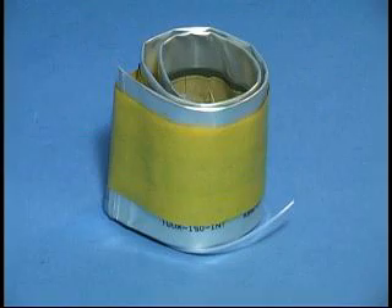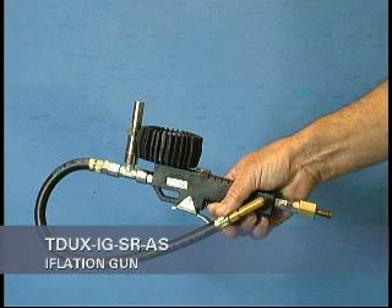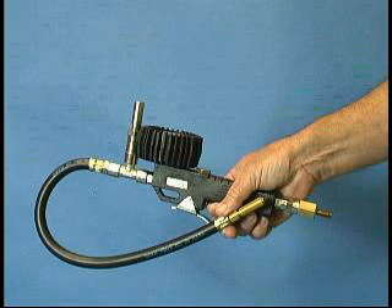One of the following inflation tools available from Tyco Electronics must be used to install the T-DUX sealing system. The T-DUX IG-SR-AS inflation gun can be connected to a pressurized air bottle or compressor. The pressure to the inflation gun should be a minimum of 60 psi and a maximum of 150 psi.